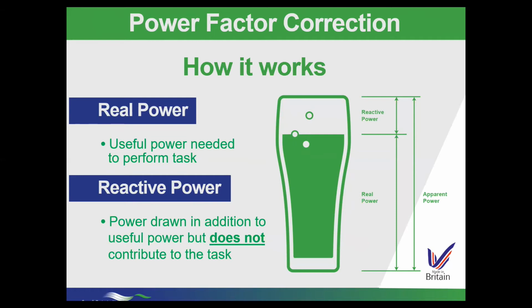Even if they've got what you call a variable speed drive or whatever, it's still a motor at the end of the day, and it's still what you call inductive. So if we can introduce an equal but opposite effect to the inefficiency of a motor, then you normally get a cancellation of energy, a cancellation of power. So if you think of a motor being inductive and you think of power factor correction being capacitive, well, inductive and capacitive are two opposites. So basically, power factor correction is introducing capacitors onto an electrical system to cancel some of the energy that's already there.